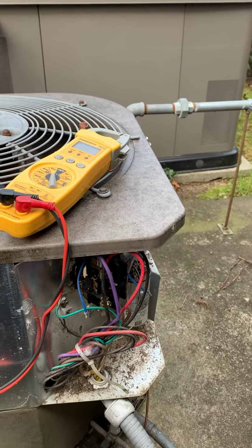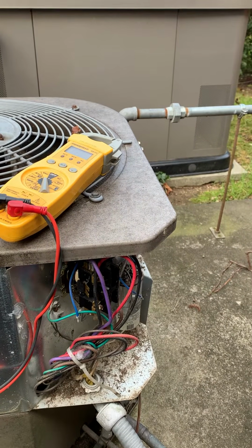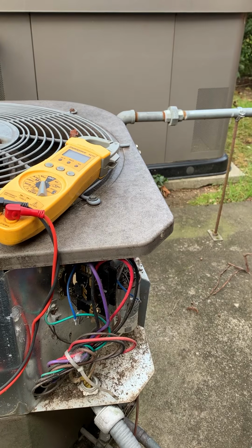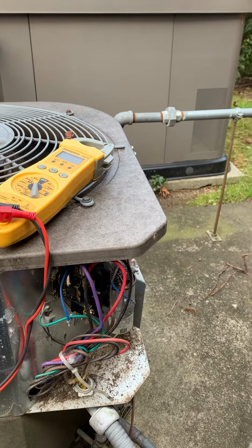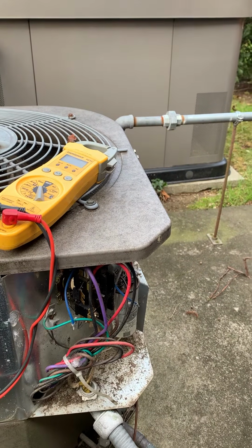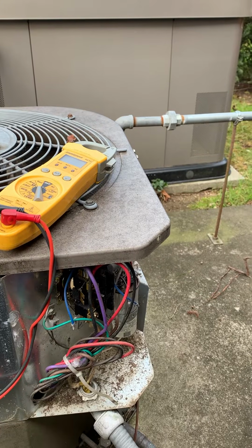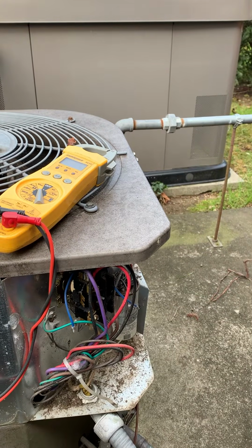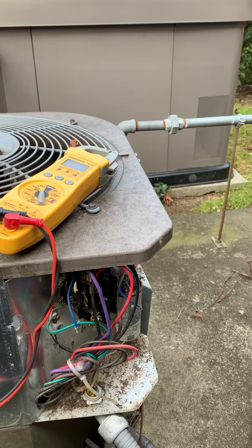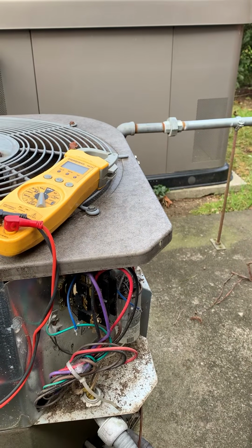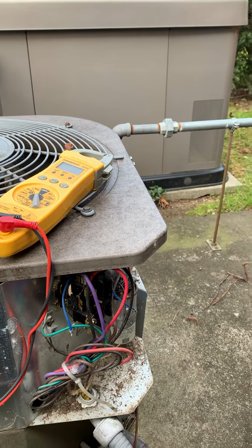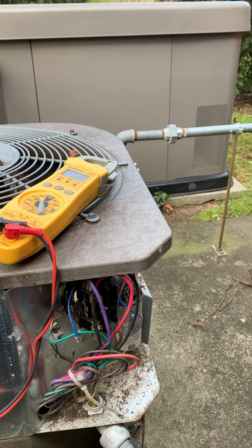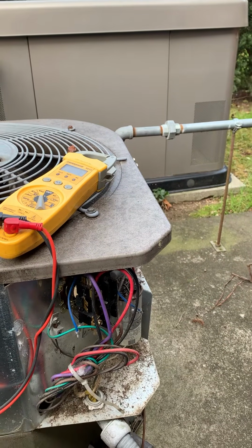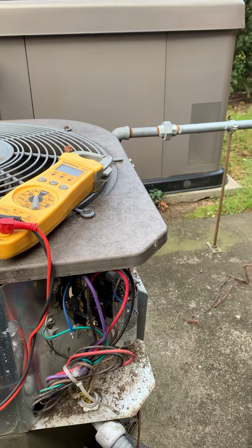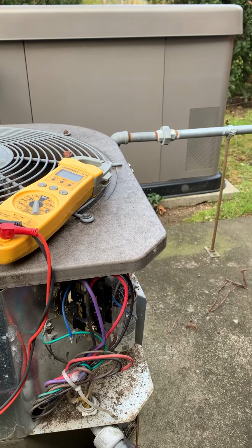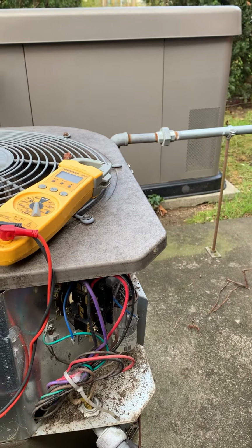So the way you can test a transformer and see how much voltage should be going through that, or amps going through that, is you're going to take, it's a 50 VA transformer, and you should take the 24 volts, divide that into the 50 VA, and then you'll get more or less right around 2 amps. That's what you should be running through, okay? A transformer that size. So you take the 24 volts, divide that into the VA, the 50, and you should more or less get around 2 amps, nothing more than that. That's why it pops around, I think it's like 3.